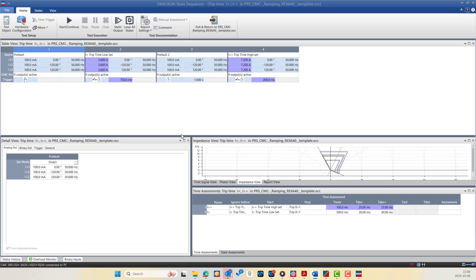The sequencer test module allows us to create and execute customized test sequences by defining a series of states — state number one, two, three, and four — each with a specific current, voltage, frequency, and phase angles. Additionally, binary output can be assigned for each state. The transition between states can occur automatically based on time delays, binary trigger signals, or manual user interaction, enabling flexible and complex testing scenarios.